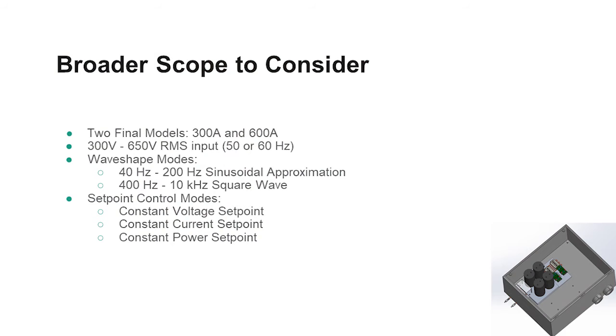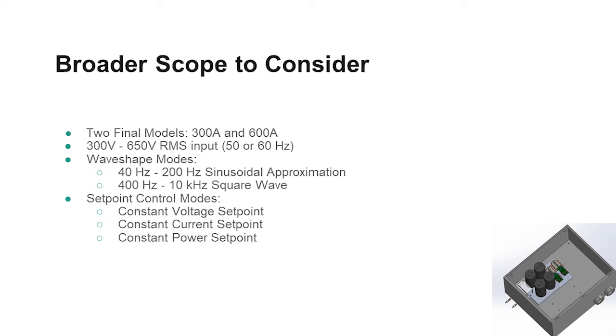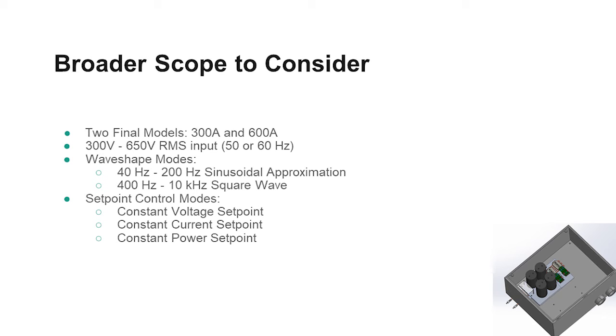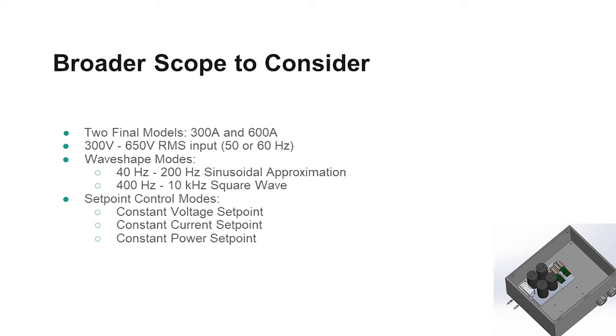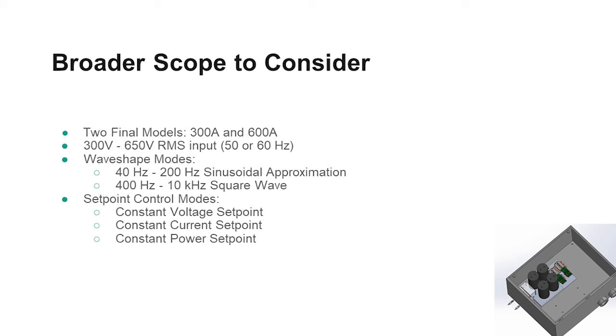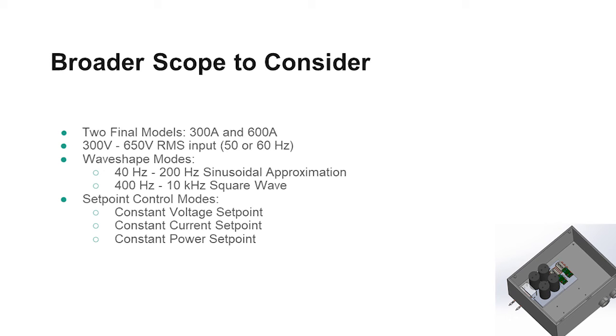While this project is just the beginning of the product development, the final product scope looks to have 2 models available for RoMan's customers. One providing 300 amps at a full voltage output, and the other providing 600 amps at a full voltage output. This output voltage is based on the 3-phase input provided, ranging anywhere from 300 volts RMS to 650 volts RMS at either 50 or 60 hertz. On the output side, there are 2 output modes, each with their own frequency range. Square wave, ranging from 400 hertz all the way up to a possible 10 kilohertz, or a sinusoidal approximation, ranging from 40 hertz all the way up to 200 hertz. In addition to these different wave shape outputs, customers will be given the option of controlling their set points based on maintaining voltage output, current output, or a constant power output.